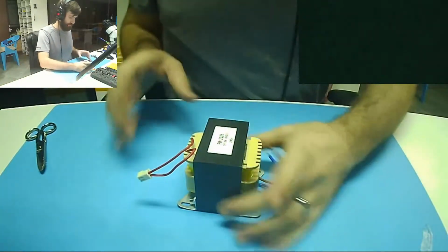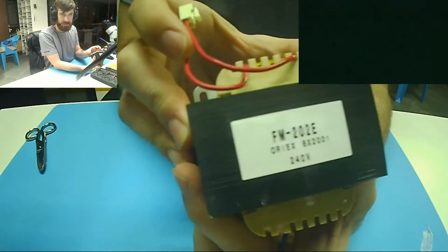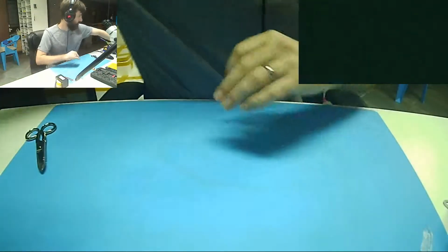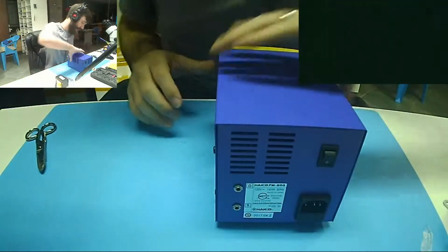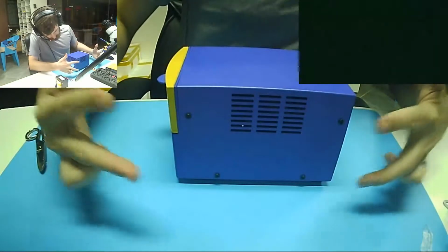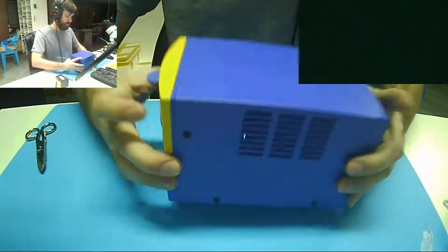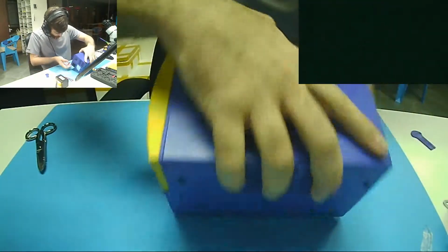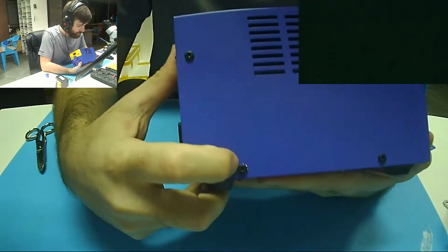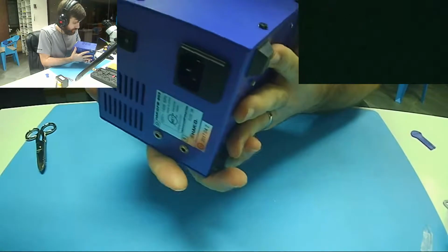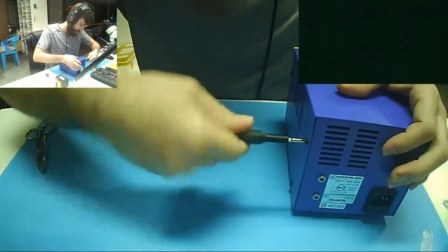So, step 1. Get yourself the transformer that you need. Step 2. Get your Hakko. It has 4 screws in each side, to a total of 8. Got the key so I don't break it. And it looks like one of them, on mine, this screw, has a lock washer on it, which is probably used for grounding, if I had to make a guess, because that cuts through the paint generally.